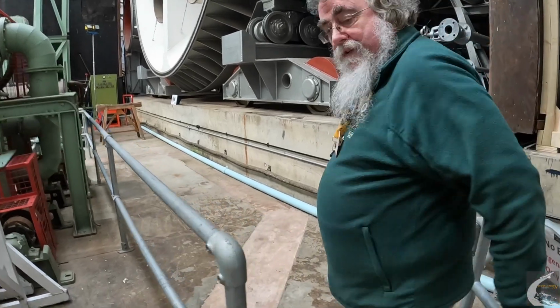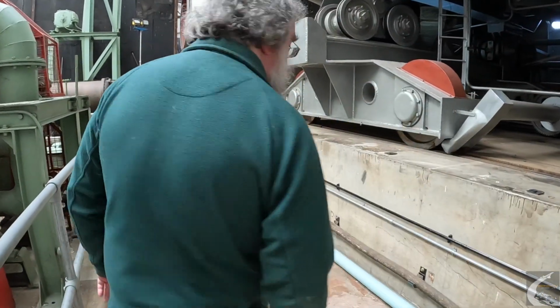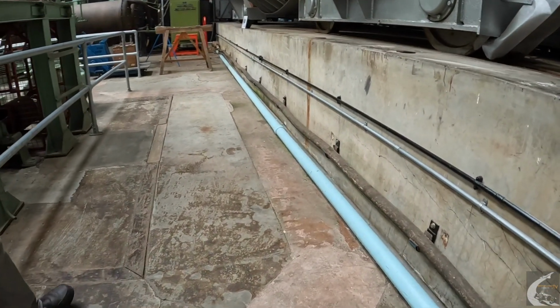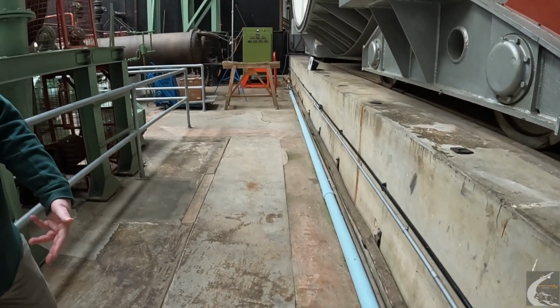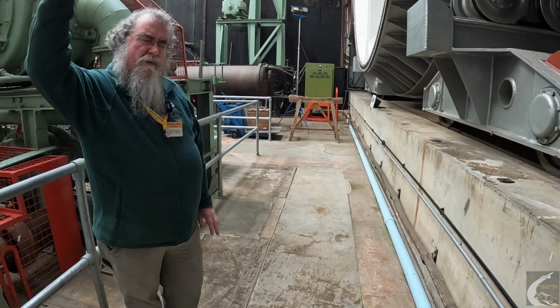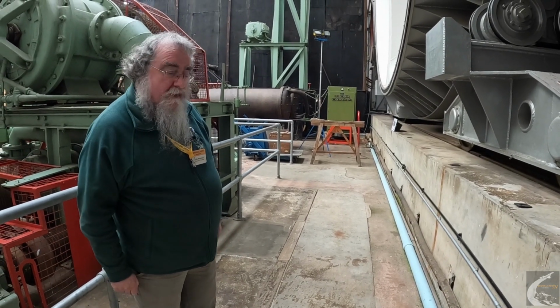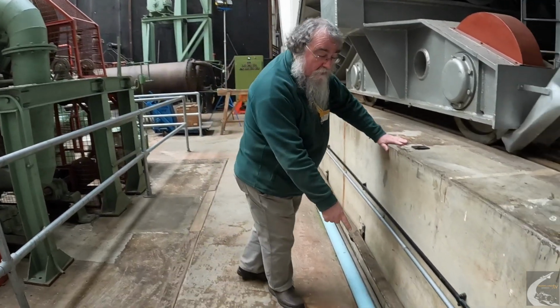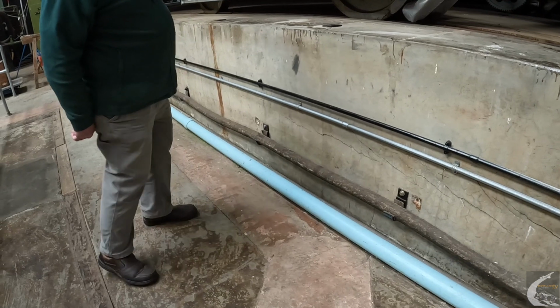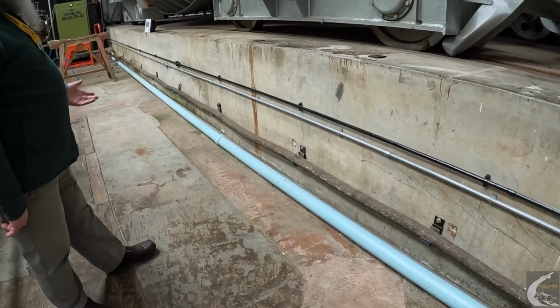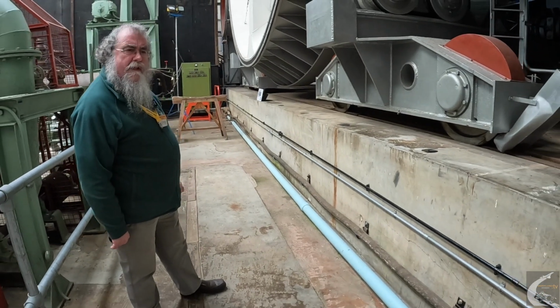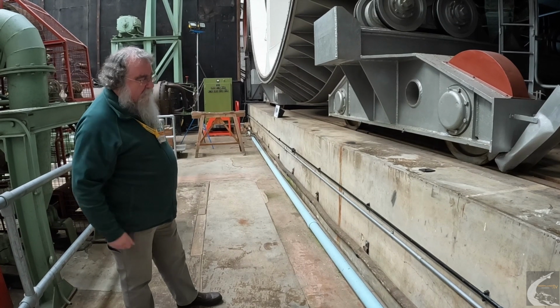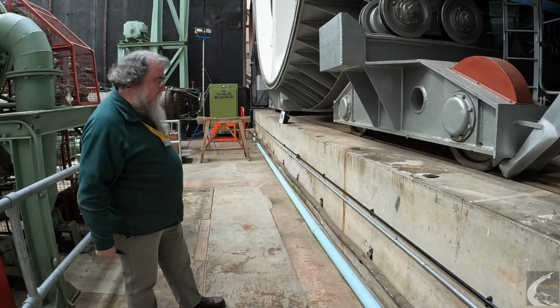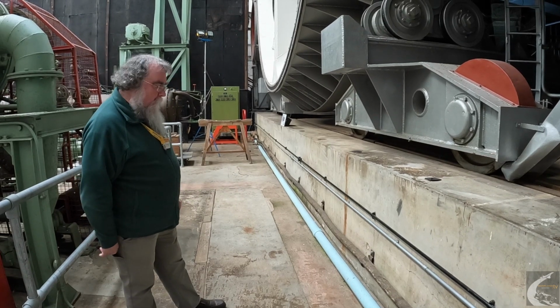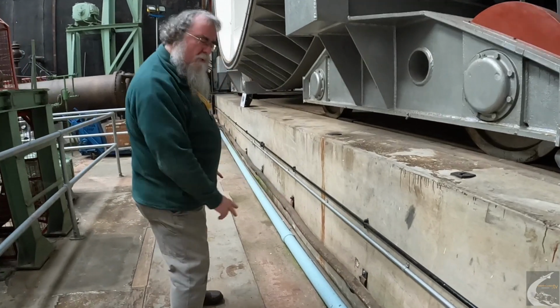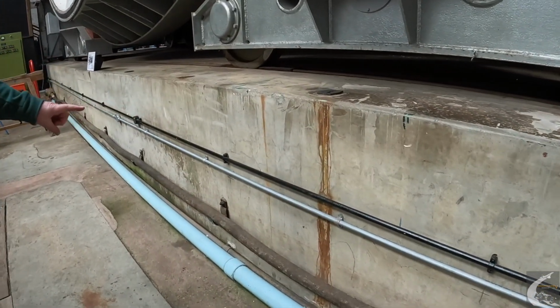If we come through the 'no authorised entry' gate - for whatever reason they decided to put a kink in the lane - but underneath there would have been, I'm sure, 4 or 5 large cables, given the number of OCBs we had up there. The type of cable is probably like the one we can see here: a very large 3-phase cable, wrapped in cloth on the outside, with bitumen inside, and armoured with steel cable wrapped around it, which is why it's quite so stiff.